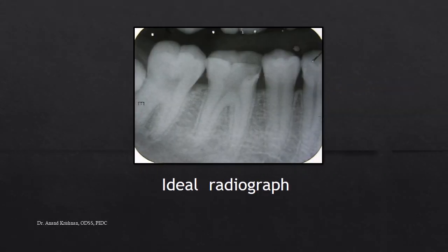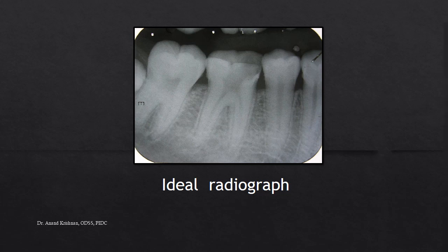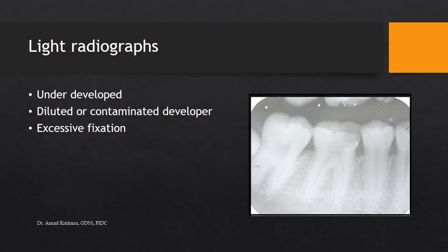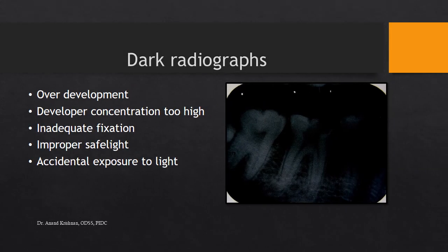Additional faults include insufficient contrast from under-development, under-exposure, excessive kVp, or film fog. Dark spots or lines occur due to fingerprints, static discharge, excessive bending of the film, or contact with developer before processing. Light spots occur when the film is contaminated with fixer before processing or contacts the sides of the processing container. Yellow-brown spots result from insufficient washing or contaminated/depleted solutions. Blurring is caused by patient movement during exposure or double exposure. An ideal radiograph should show individually distinguishable structures with clear sharpness and well-represented lesions.